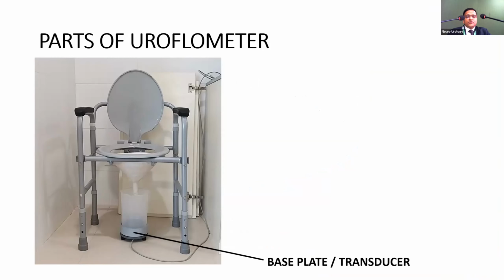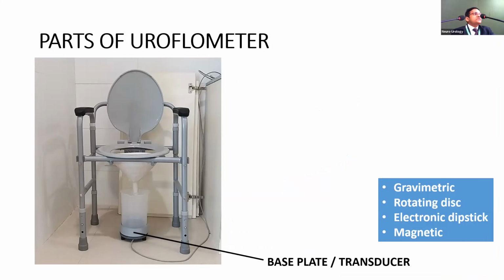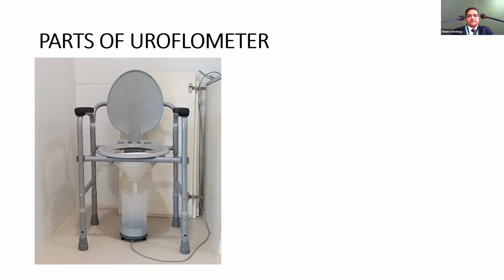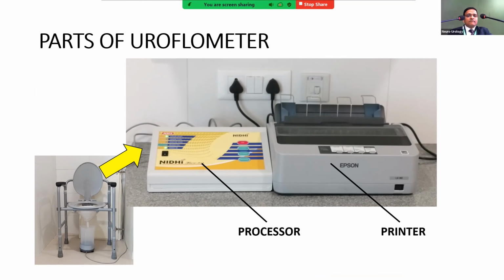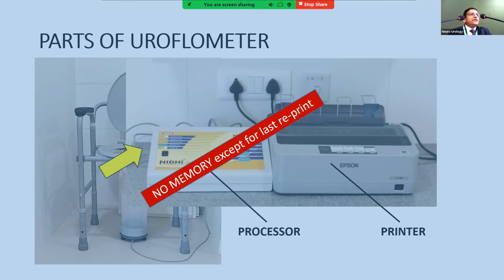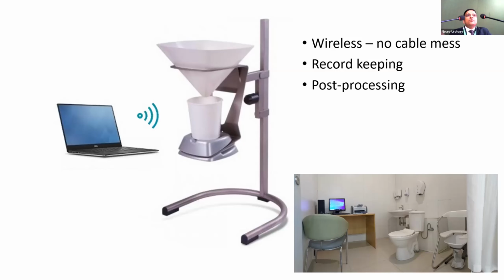Parts of the uroflowmeter: you have a base plate or transducer. Various types are available. Most commonly, gravimetric or rotating discs are available in the market, and out of these, the most common is gravimetric. There's a beaker, a funnel, a comfortable seat. Then you either have a basic uroflowmeter with not a lot of customizable software, with a processor and an automatic printer. These are very cost effective and practically useful, but the problem is that if there is any error, apart from the last reprint, you don't have any data left. Then you have more sophisticated machines, whether wired or wireless.